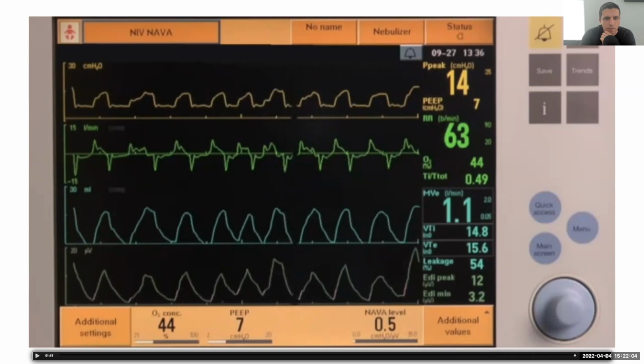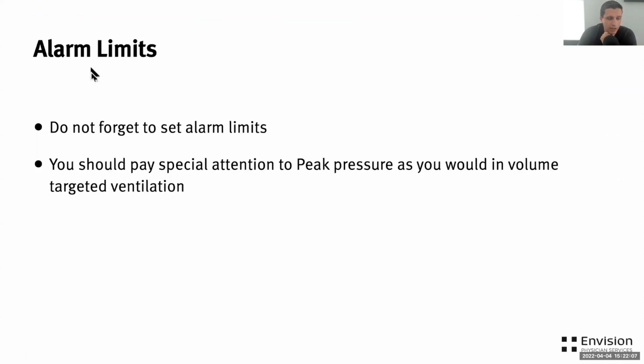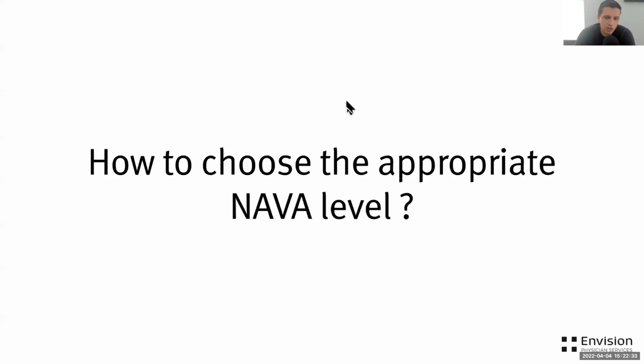Okay. The last thing we need to talk about are alarm limits. Don't forget to set them appropriately, but you should, a bit like volume guaranteed, pay special attention to peak pressure. And the reason being that you do not want to allow the vent to reach really unreasonable peak pressures when delivering NAVA ventilation. So obviously the big question is, how do we choose the appropriate NAVA level? Where do I start? How much do I go up? How much do I go down? And that's the last, and I guess the most important setting that we have to pick on these vents.